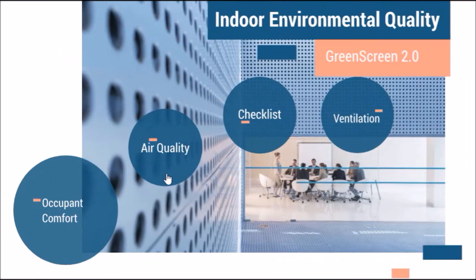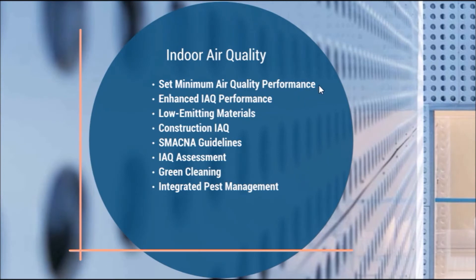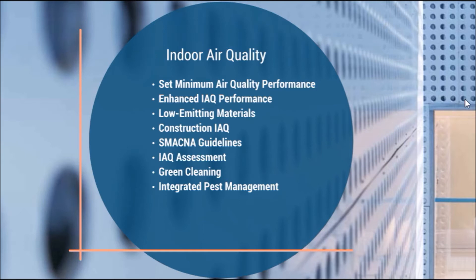Now we head into air quality itself. We want to set the minimum air quality performance according to the prerequisite. Mechanical and natural ventilation standards must be in place under ASHRAE 62.1. For enhanced IAQ strategies, these can use mechanical, natural, or usually mixed-mode ventilation. Mechanical ventilation uses an HVAC or mechanical system, whereas natural ventilation uses passive designs and operable windows. Controlled tobacco smoke is very important — smoking areas must be placed at least 25 feet away from a building's air intake or operable windows so smoke doesn't enter the building.